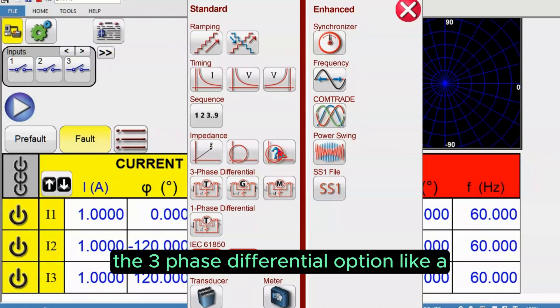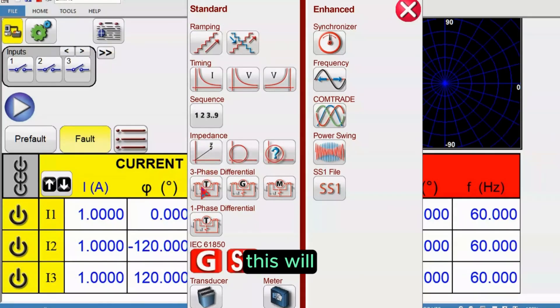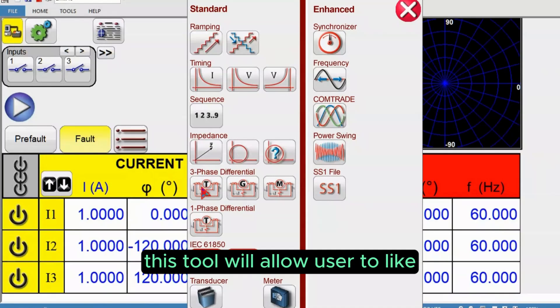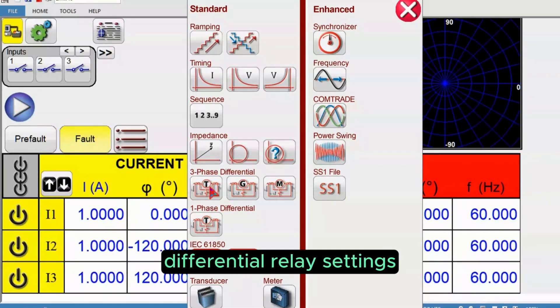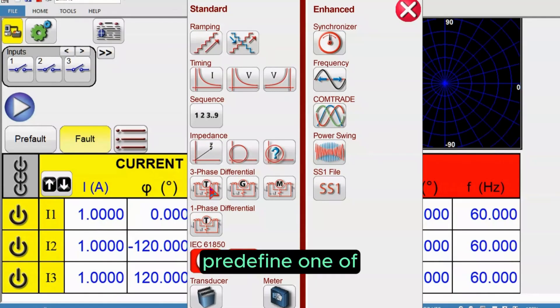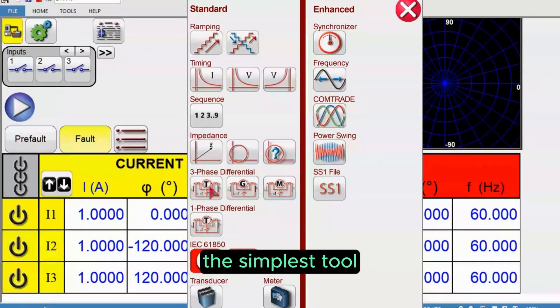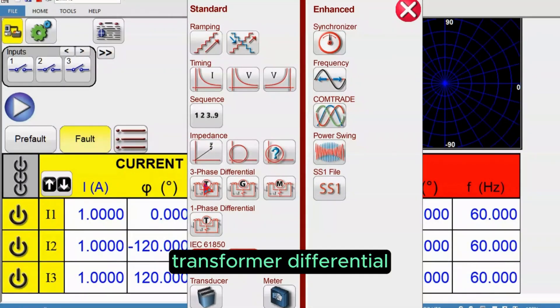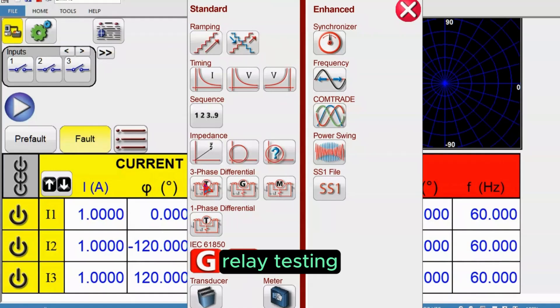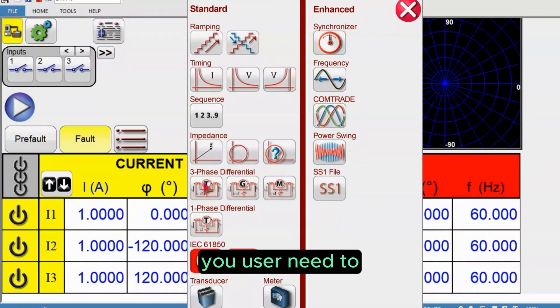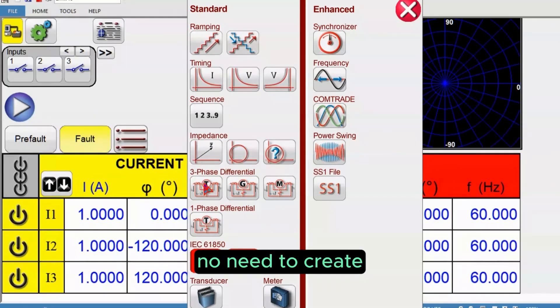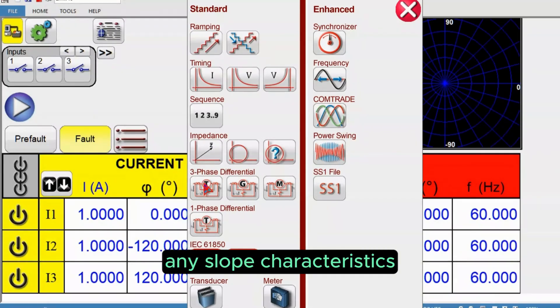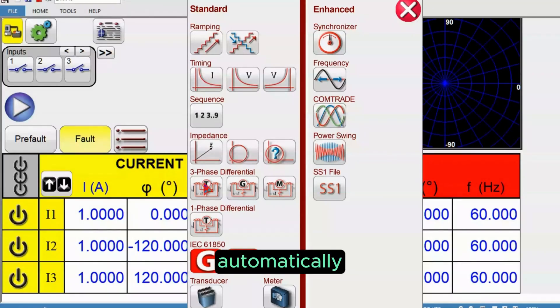The three-phase differential option, like the transformer test, this tool will allow users to enter your transformer differential relay settings and run the test. This is one of the simplest tools for transformer differential relay testing. You only need to enter the relay settings, that's it. You don't even need to create any slope characteristics, the software creates it automatically.